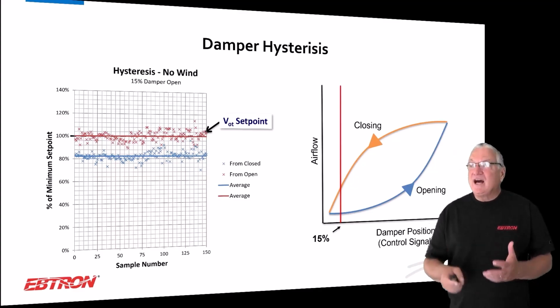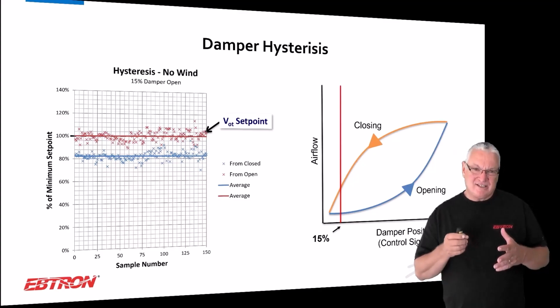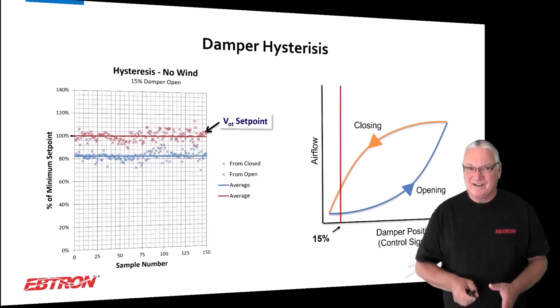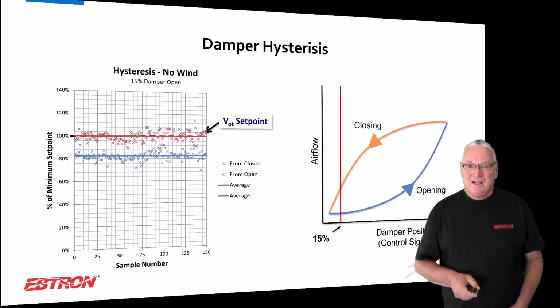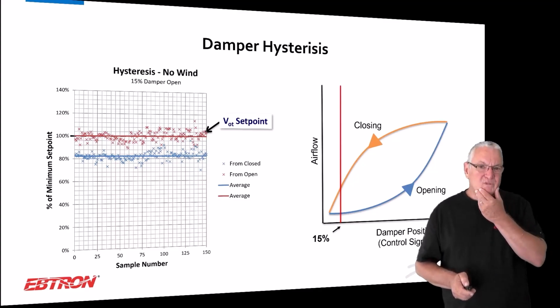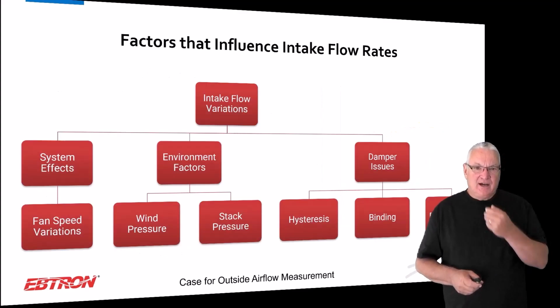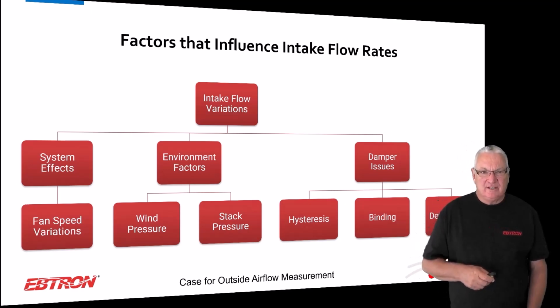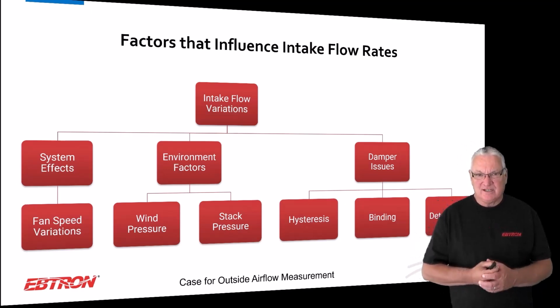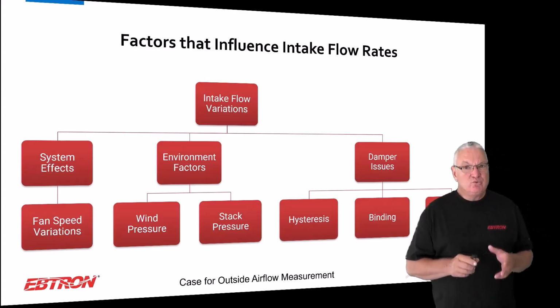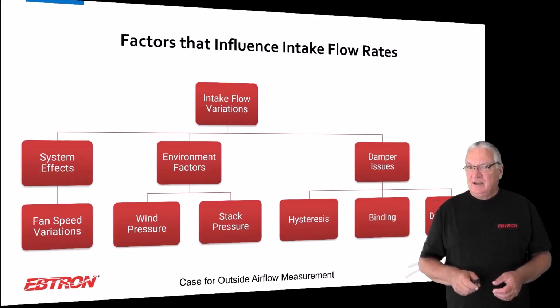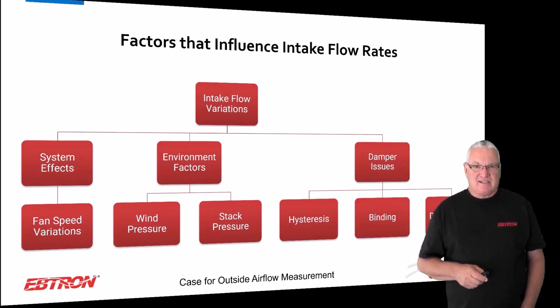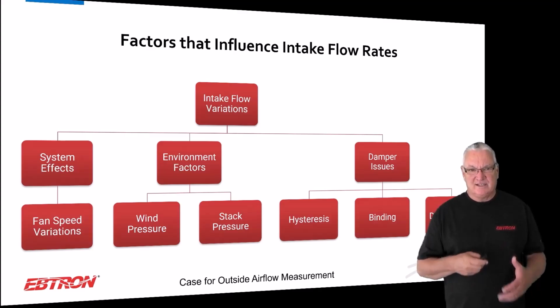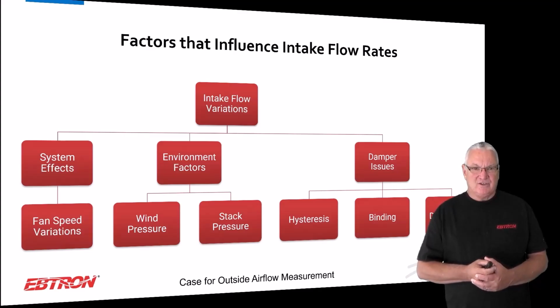So again, you can't rely on damper position. It's not just in outside air intakes either. It's everywhere. It doesn't work, so we have to compensate for that. When you look at all these different factors that influence intake flow rates, you really should come away from this saying, I need to figure out how much outside air I have coming into this system, and I'm going to need to control it. That's really where I want you to be right now.